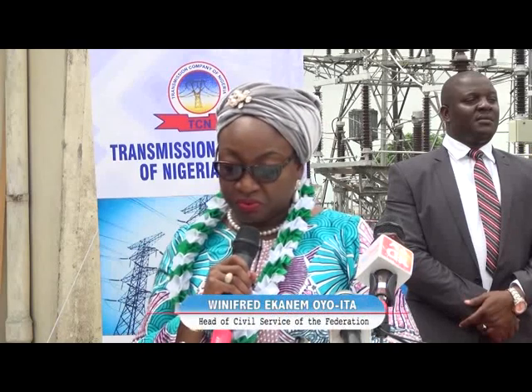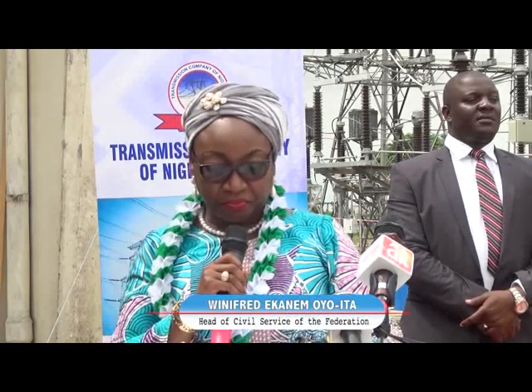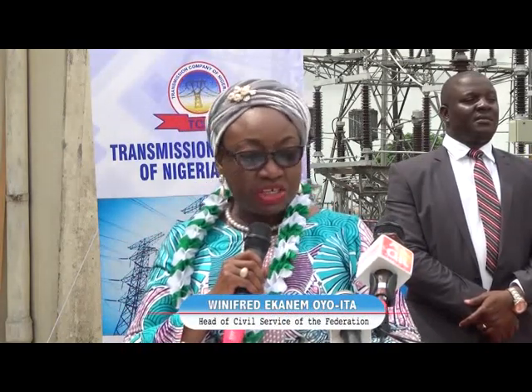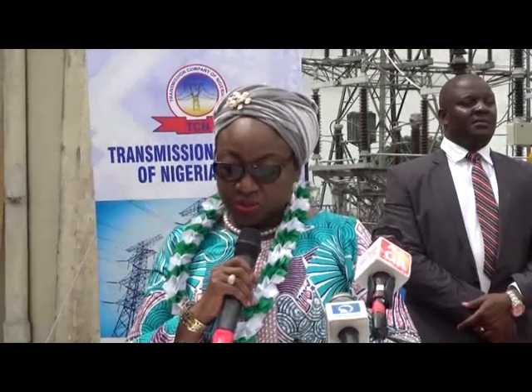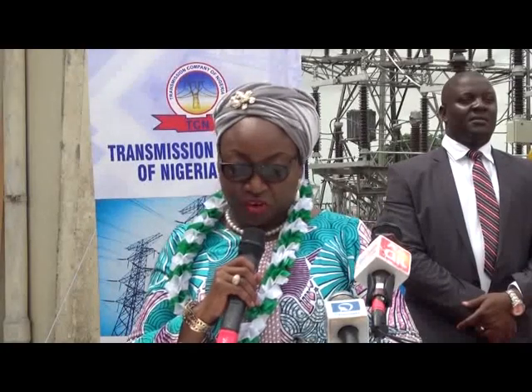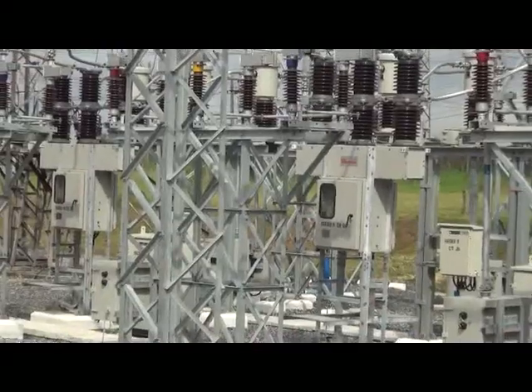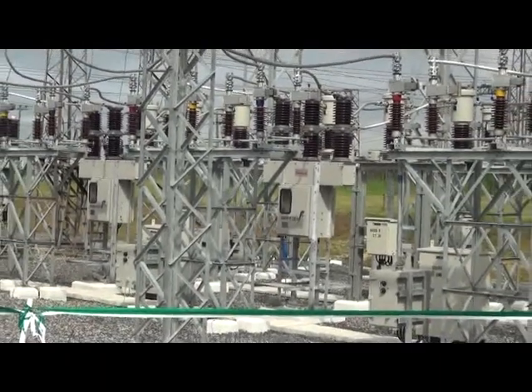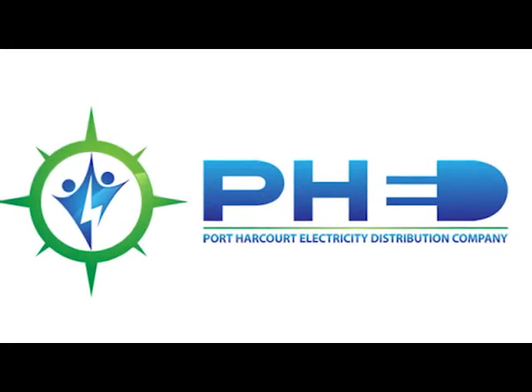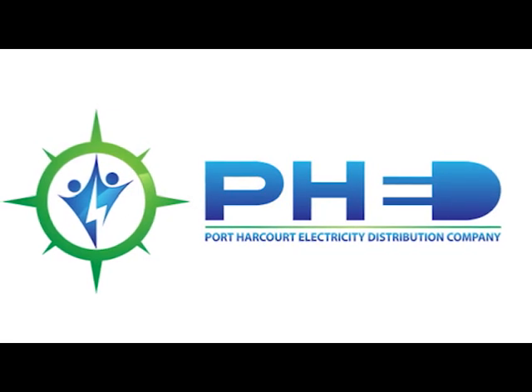With this installation, the capacity has been raised to 240 MVA. With the commissioning of the 1x60 MVA, 132/33 kV transformer, she said the upgraded transmission station is expected to improve power supply for customers of the Port Harcourt Electricity Distribution Company across 10 key areas in the state.